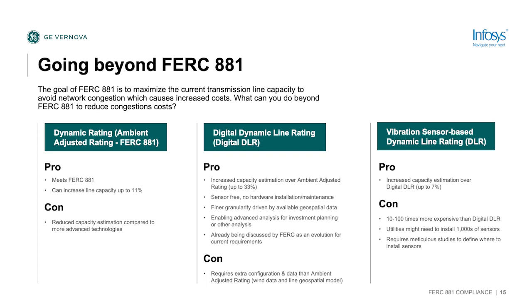And then your field-based dynamic line rating sensors can increase capacity about 7% above the digital dynamic line ratings because they've got a lot more granularity with the data that they're collecting, but they're more expensive and there's a lot more downtime and a lot more installation costs. And then there's the future overhead and maintenance cost of maintaining those devices in the field.